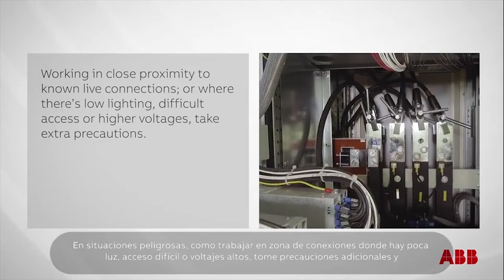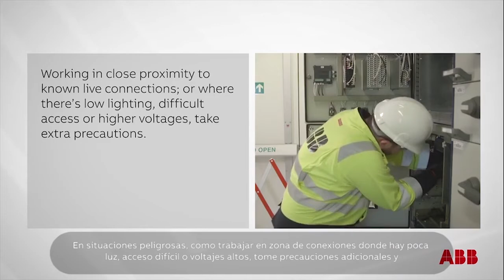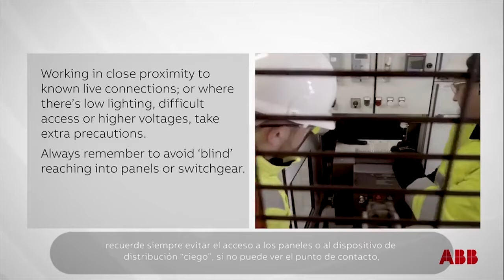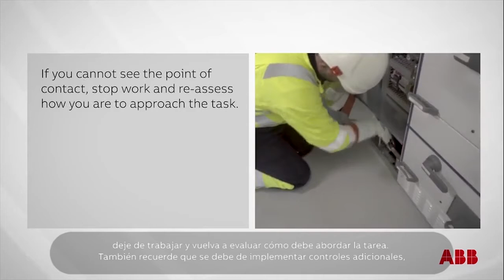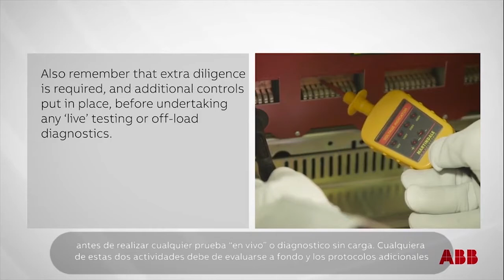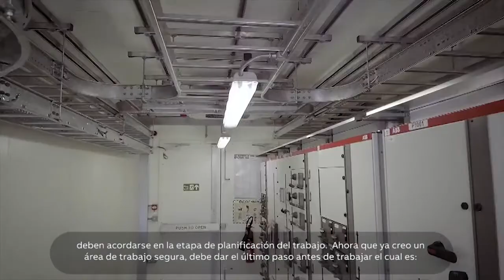In especially dangerous situations, like working in close proximity to known live connections or where there's low lighting, difficult access or higher voltages, take extra precautions. Always remember to avoid blind reaching into panels or switchgear. If you cannot see the point of contact, stop work and reassess how you are to approach the task. Also remember that extra diligence is required and additional controls put in place before undertaking any live testing or off-load diagnostics. Any such activities must be thoroughly risk assessed and any additional protocols agreed at the job planning stage.